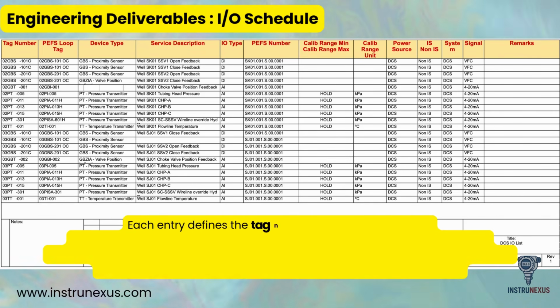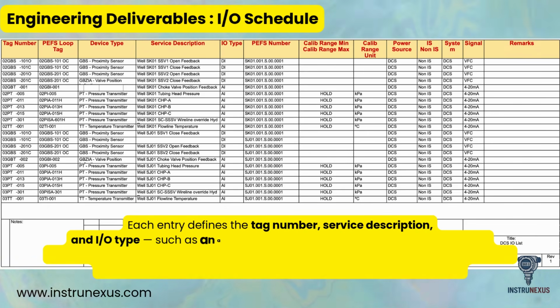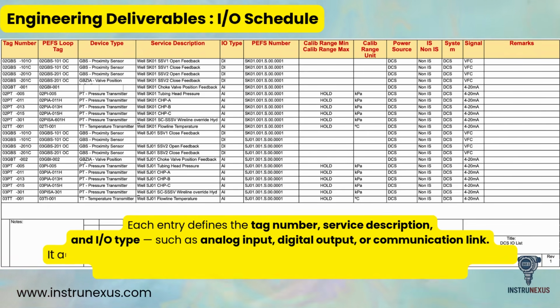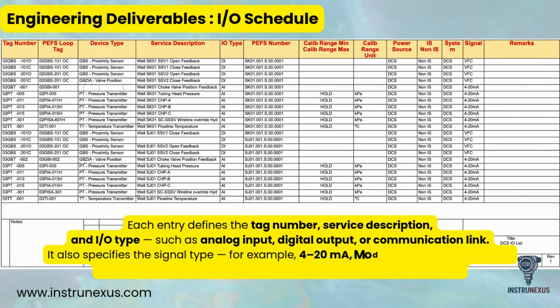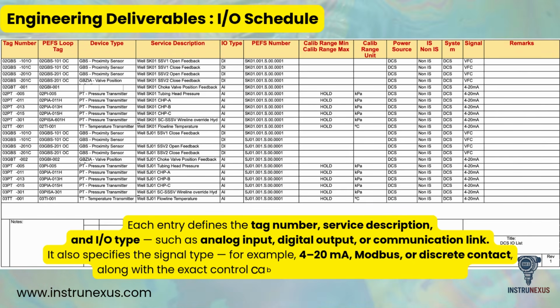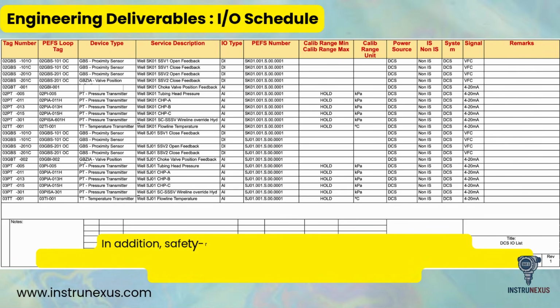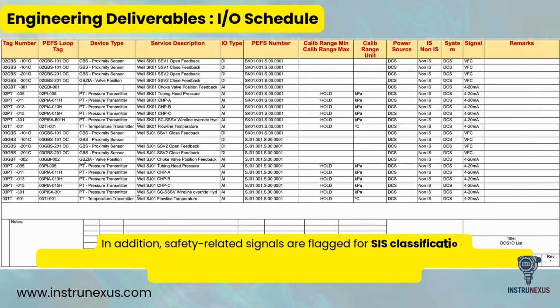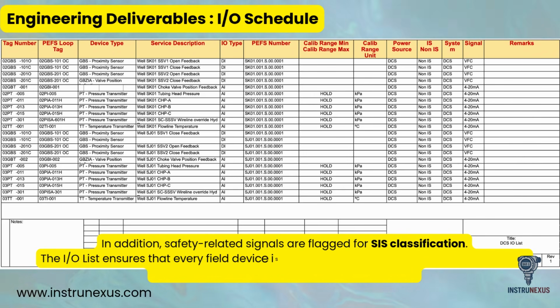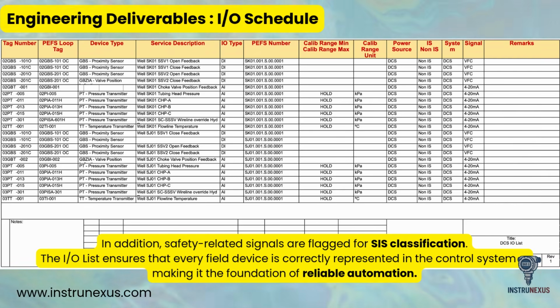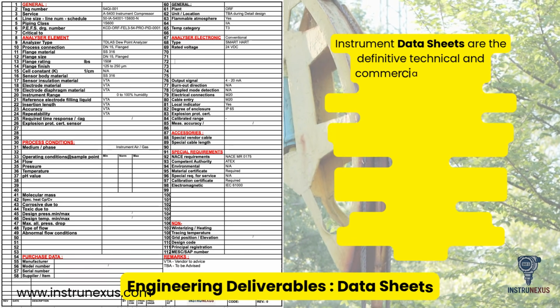Each entry defines the tag number, service description, and I/O type, such as analog input, digital output, or communication link. It also specifies the signal type, for example 4-20 mA, Modbus, or discrete contact, along with the exact control cabinet, module, and channel address. In addition, safety-related signals are flagged for SIS classification. The I/O list ensures that every field device is correctly represented in the control system, making it the foundation of reliable automation.